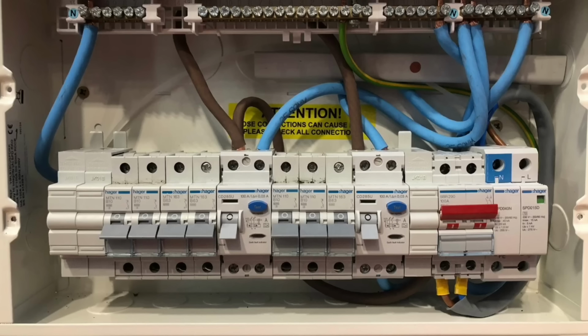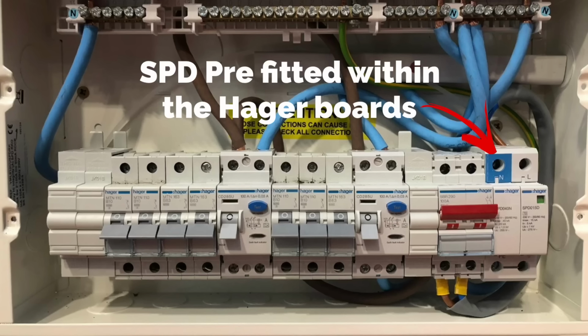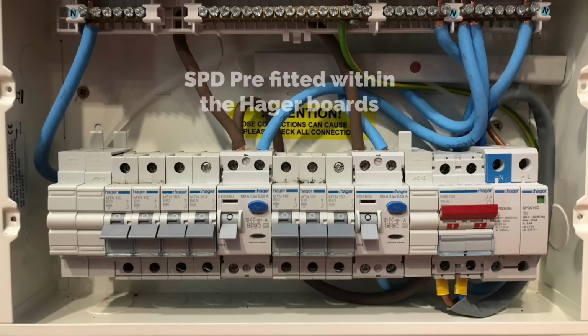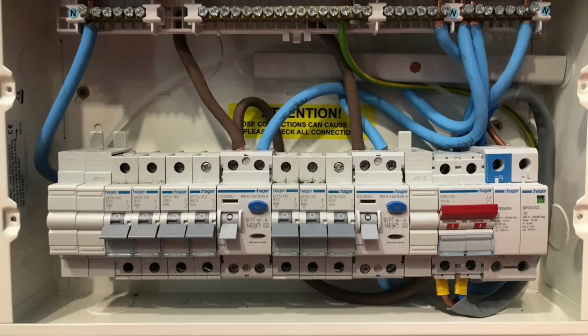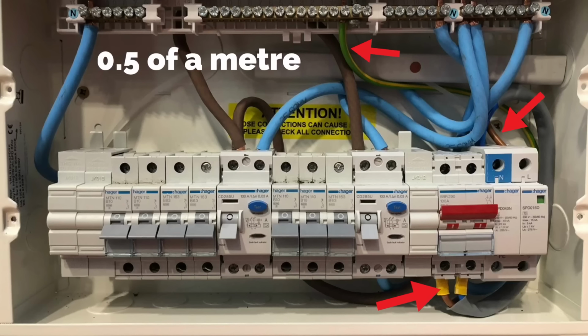Now, obviously, surge is a big discussion within the industry at the moment, and there are all kinds of feelings flapping around about this. But what I love about this is the fact that the decision's made for you. Just buy this board. All the calculations have been done. It's all in place. You don't have to worry about it. And also, because of the way that this is mounted within the board, we're falling within that half metre. The half a metre counts from this space here, so the line conductor to it, plus the earth away to the earth bar. Those two combined distances would hopefully be under half a metre, and you can see we're well under half a metre of those two distances there.